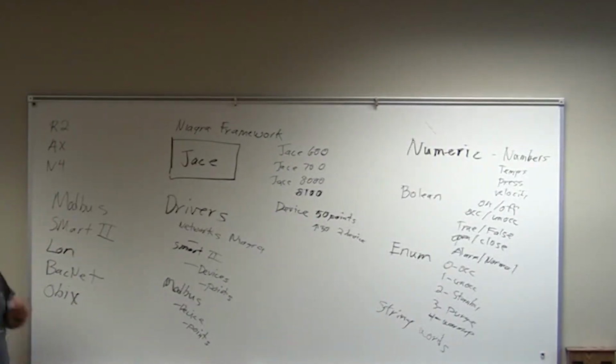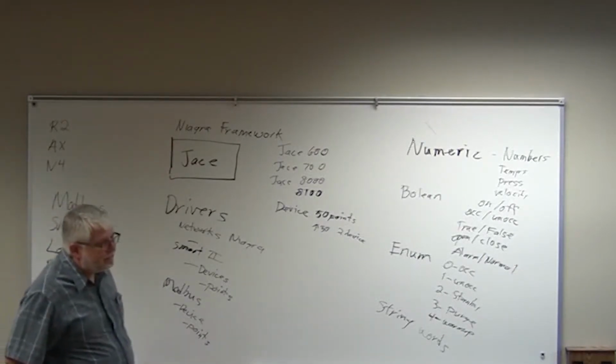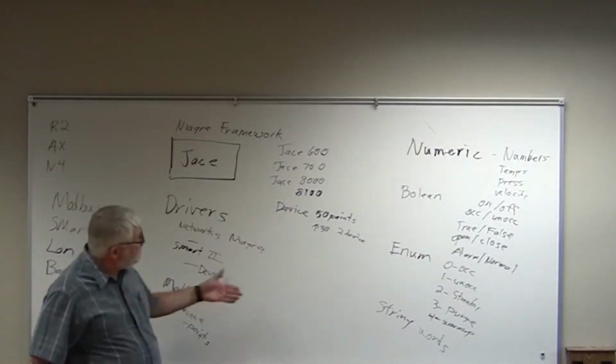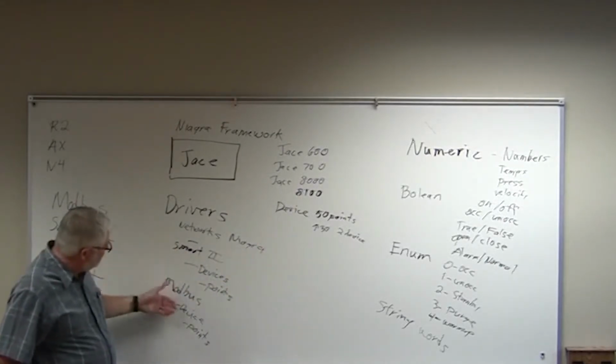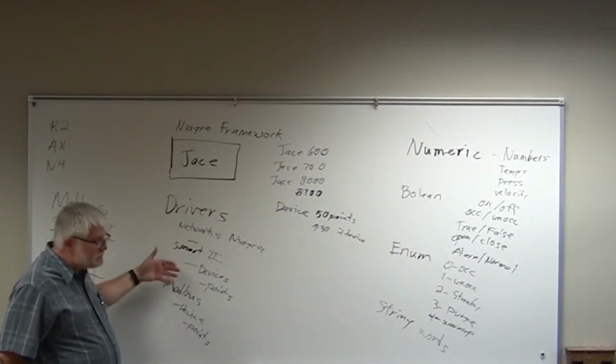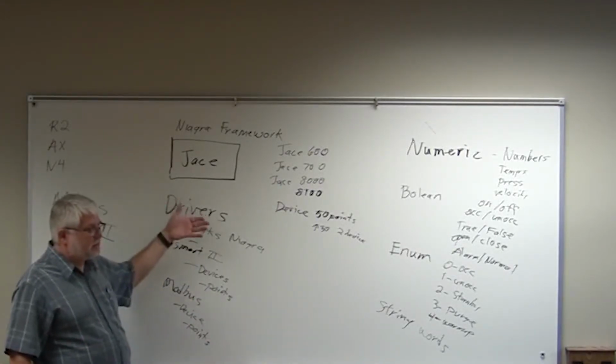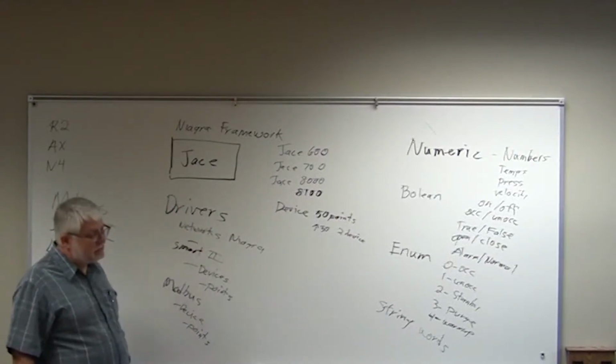So is it possible to put a router under it so that it can bring in more points than it exceeds? If you get it to the software state, it doesn't count anymore. Well, if you put another device underneath, like a BACnet device, and you were talking to other things, if you're pulling those points up into the Jace, they'll count as I/O points, because it's still connected to a controller.